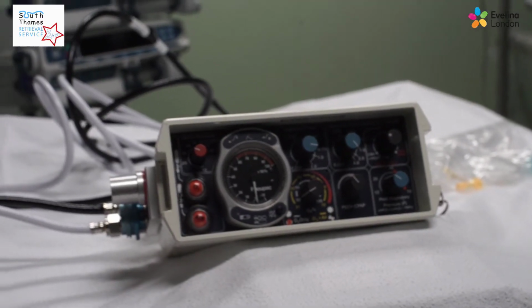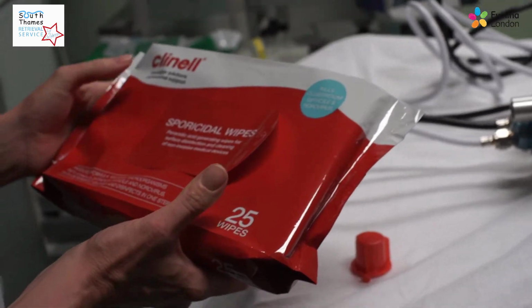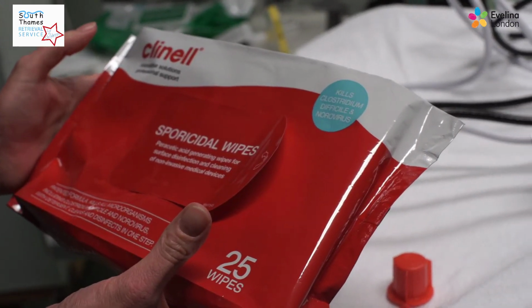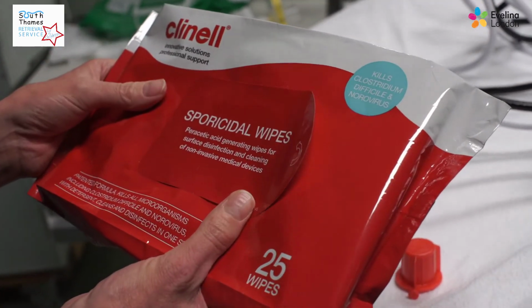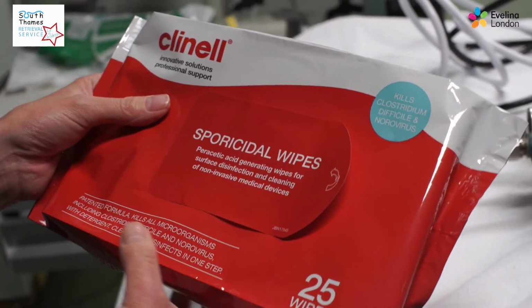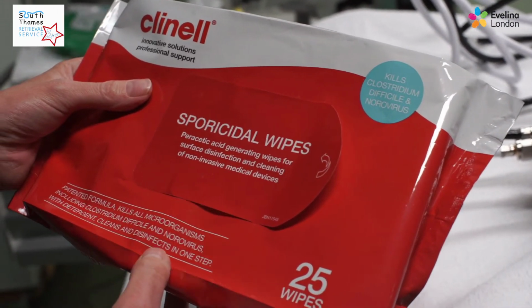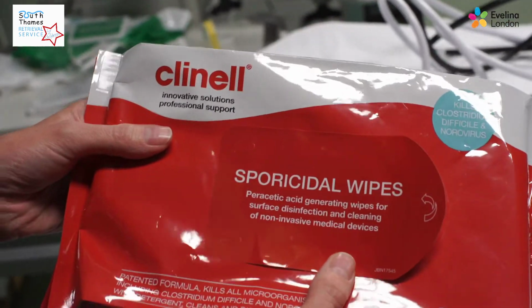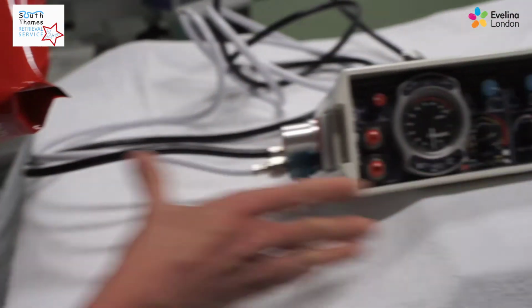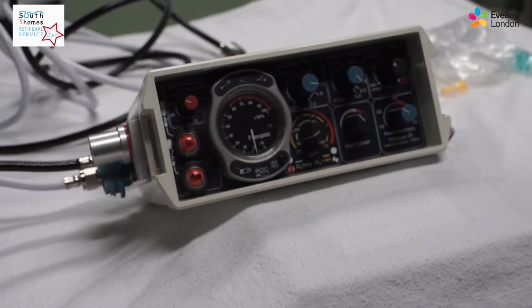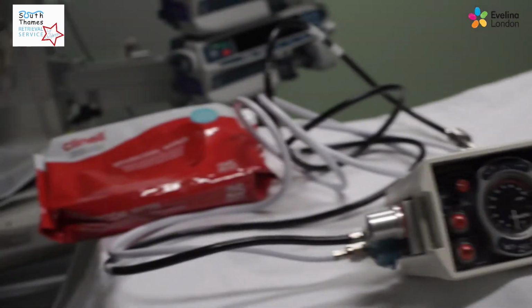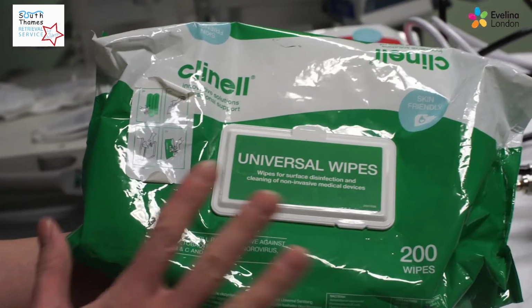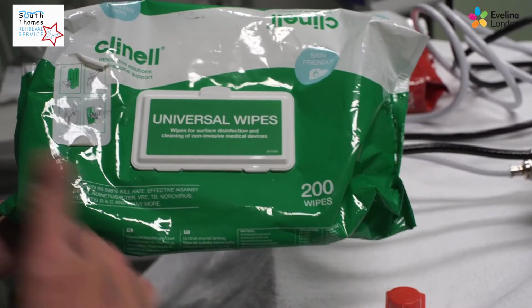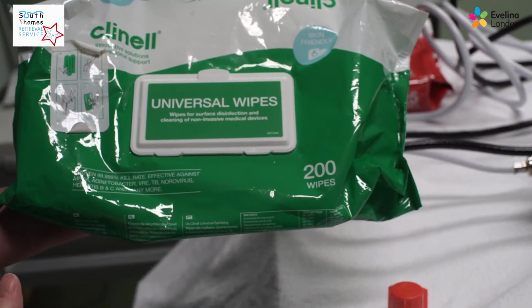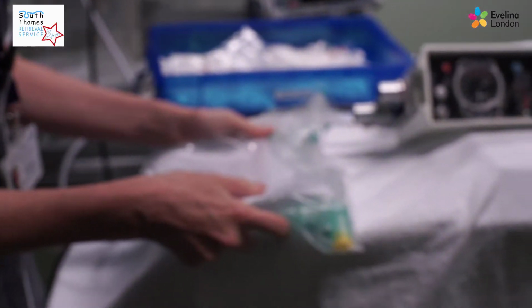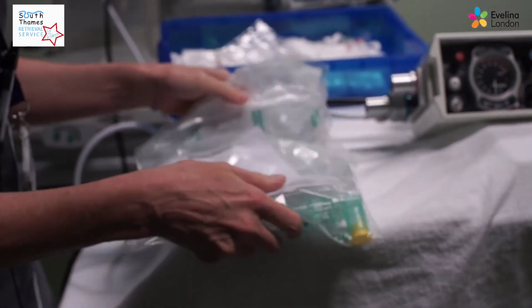Once you've removed all the removable parts, it's then time to clean the ventilator. For infections including Clostridium difficile and norovirus, we would use sporicidal wipes, cleaning the box and all the tubing. For all other uses, we would use just our universal wipes to wipe it down and allow it to dry naturally in the air. Babypac up, ready to deliver CPAP to a patient.